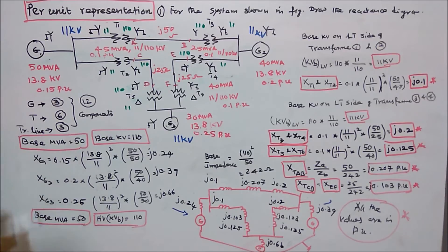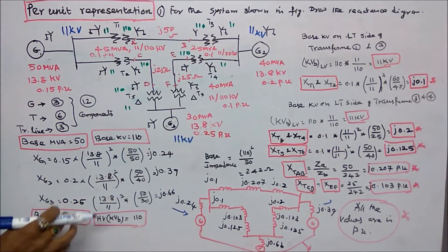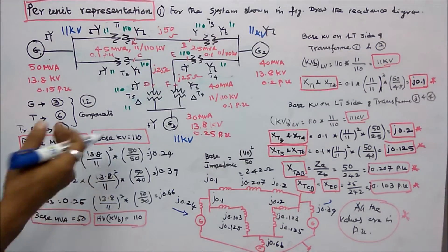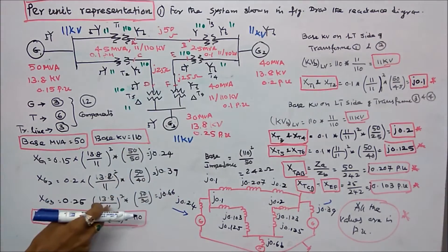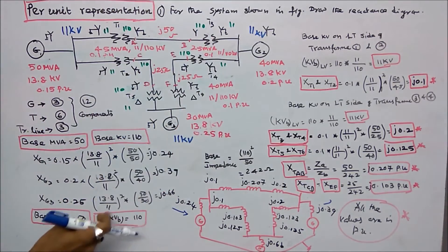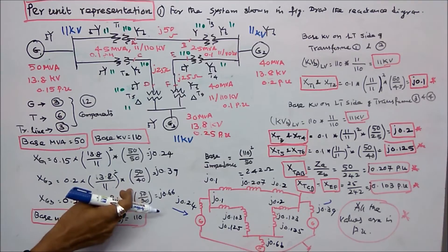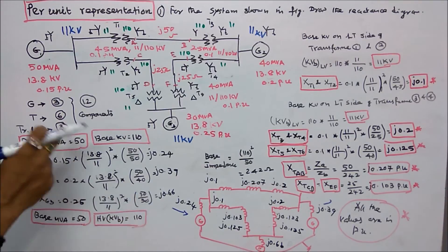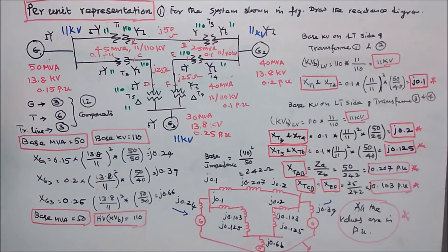Generator 3 given value is 0.25 per unit reactance. New per unit = 0.25 × (13.8/11)² × (50/30) = j0.66.